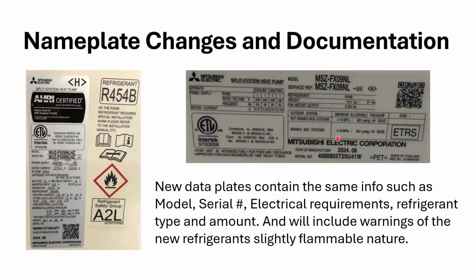Indoor unit over here, and you're going to see your information on that. Now, the location of where you're going to see that 454B could be different, and I'll show you coming up where they're going to put that notice. But what they list on it has changed a little bit. The serial number, we'll talk about that too. You'll notice the serial numbers are unique now to the specific model. If I remember right, it's 14 characters now. So a longer serial number, but unique to the particular model. Before, one serial number could go to multiple models. That's how they used to do it.